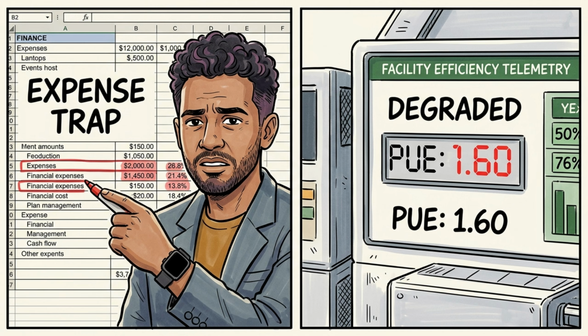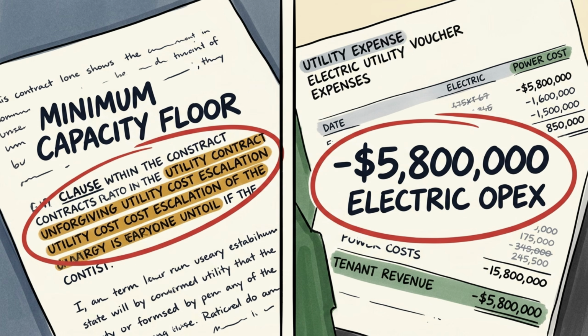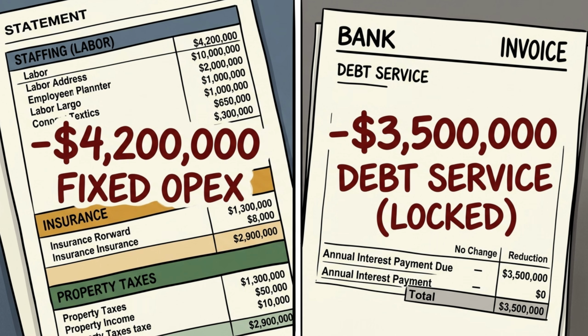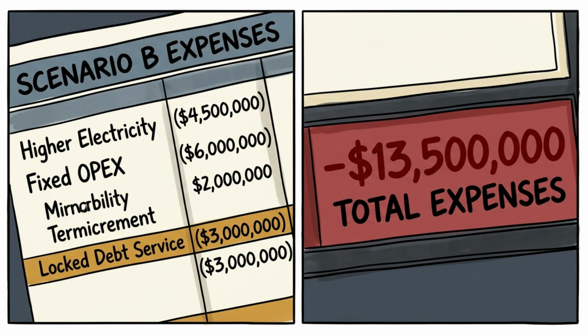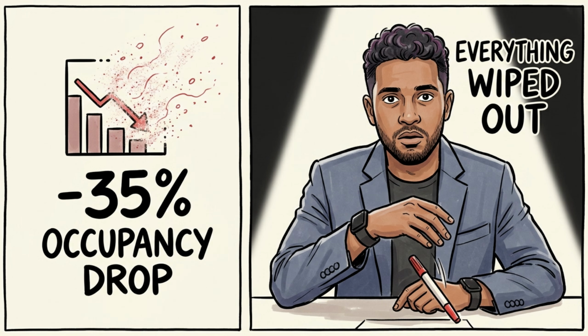But look at your costs. Because your facility is operating at partial capacity, your cooling efficiency degrades to a PUE of 1.6, and minimum utility grid reservation charges remain in full effect, pushing your electric bill up to $5.8 million. Fixed staffing, insurance, and taxes drop only slightly to $4.2 million, while your debt service remains stubbornly locked at $3.5 million. Total expenses come out to $13.5 million.